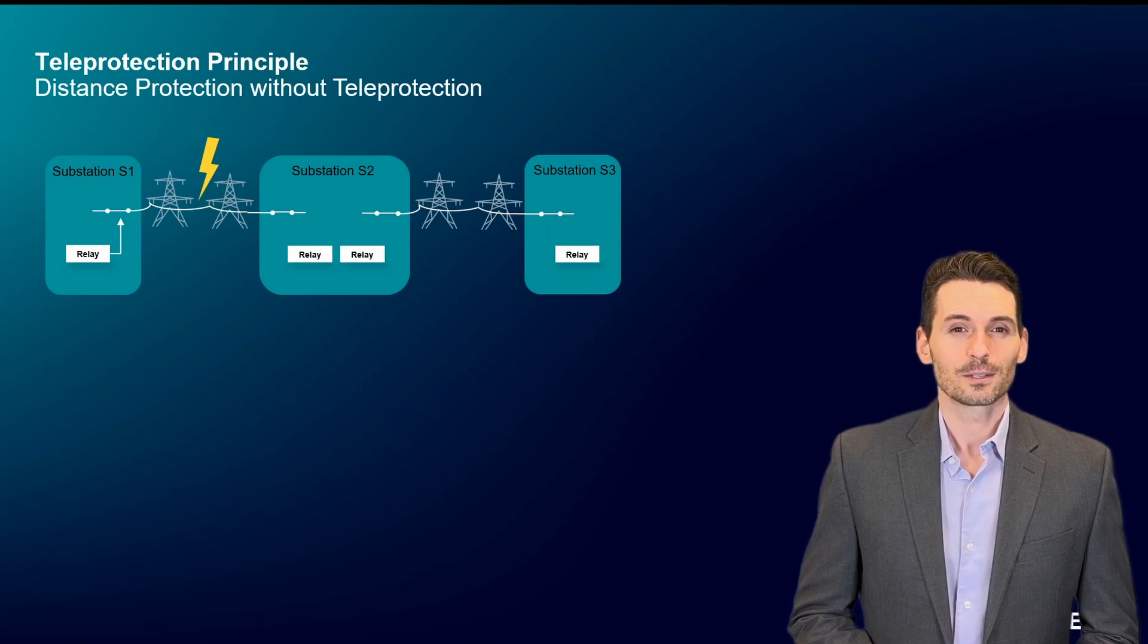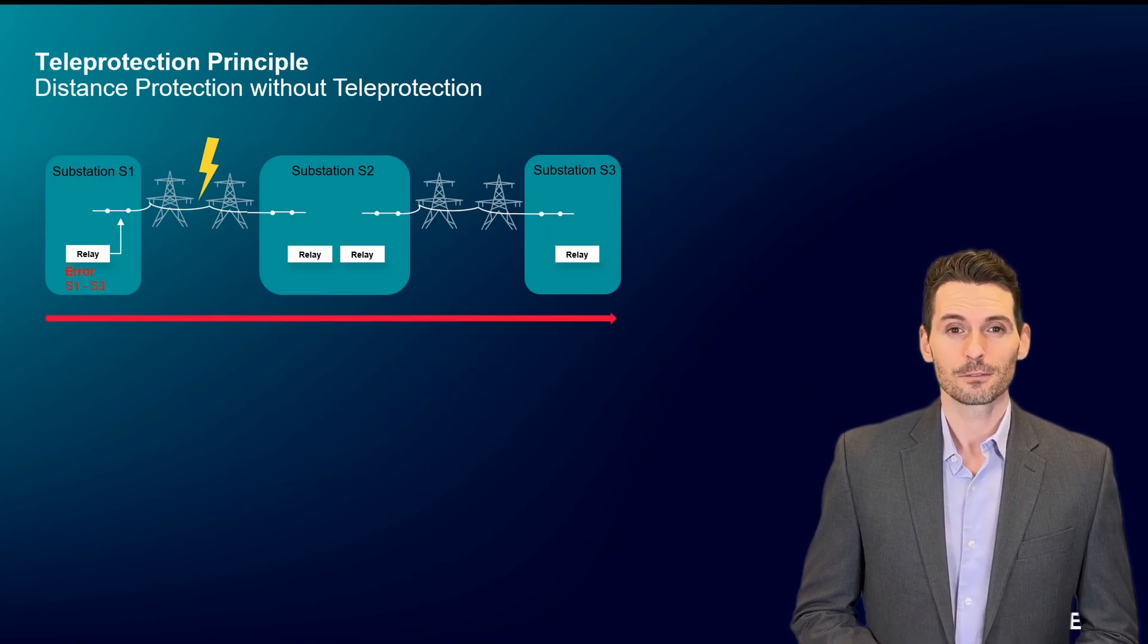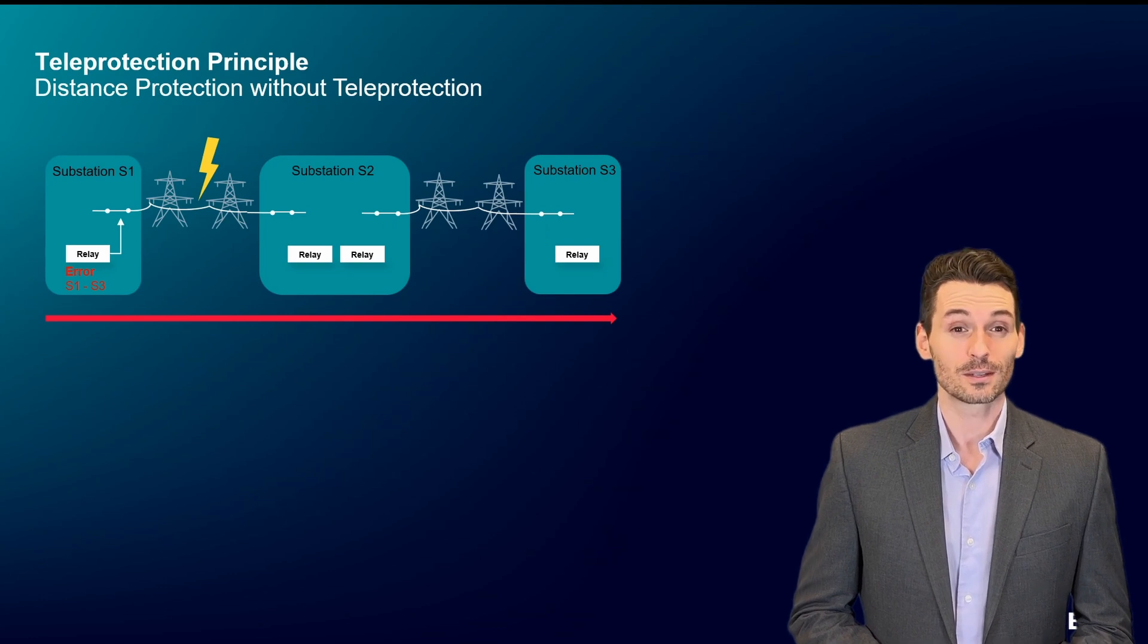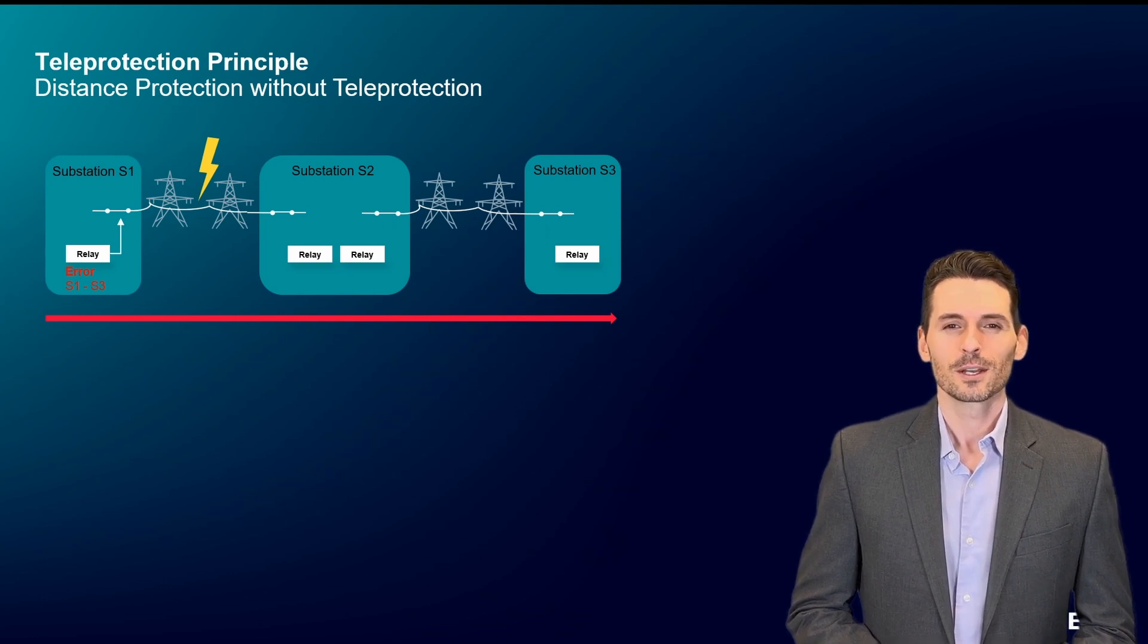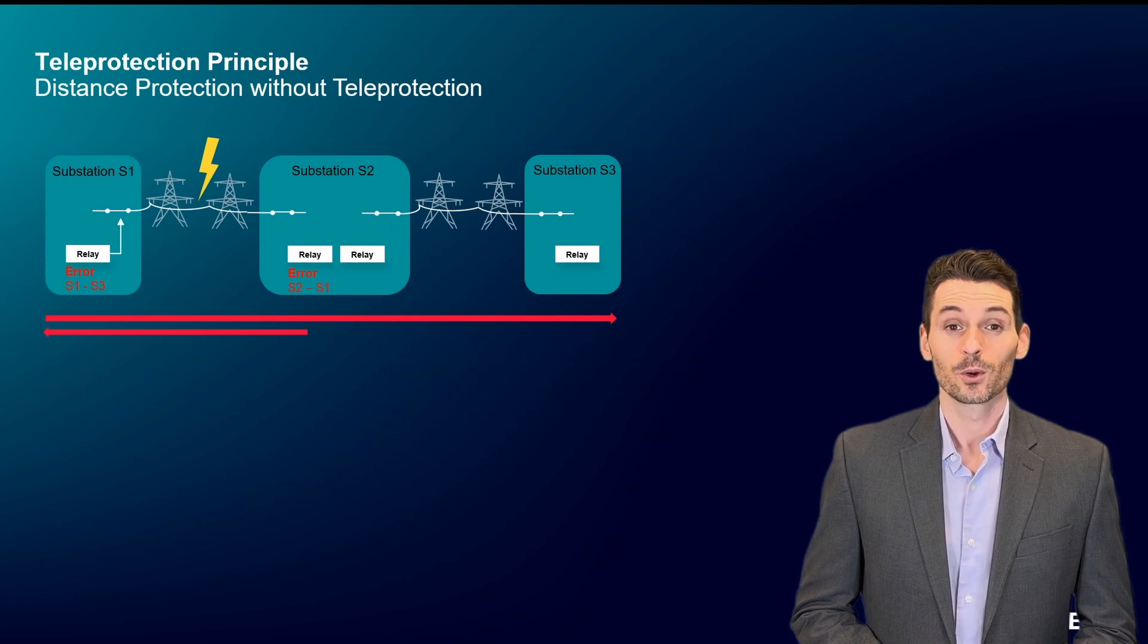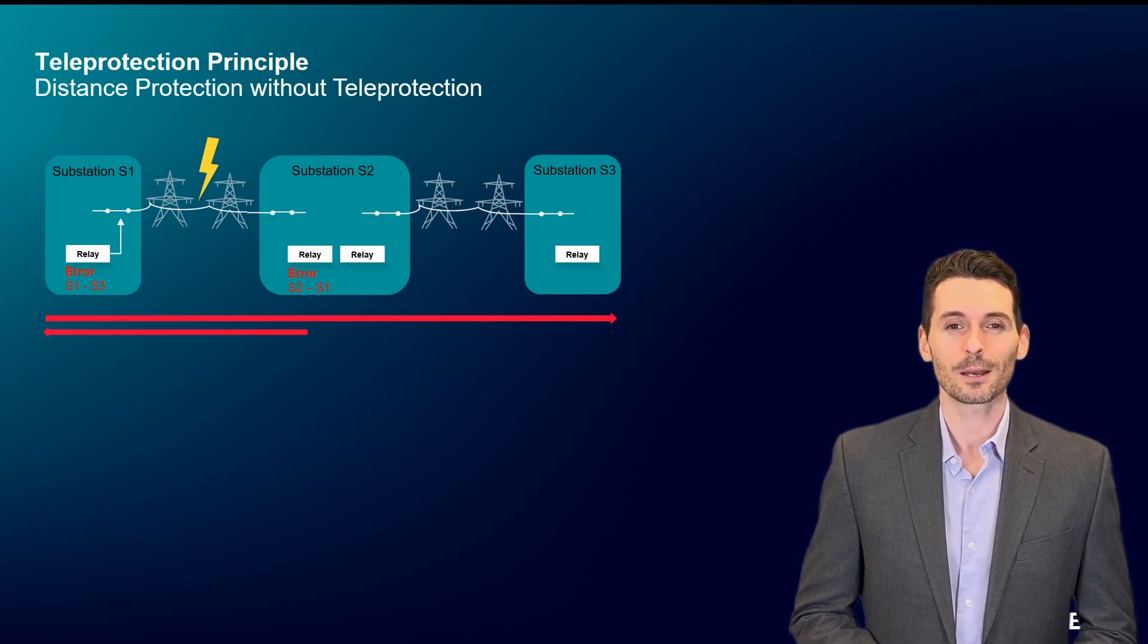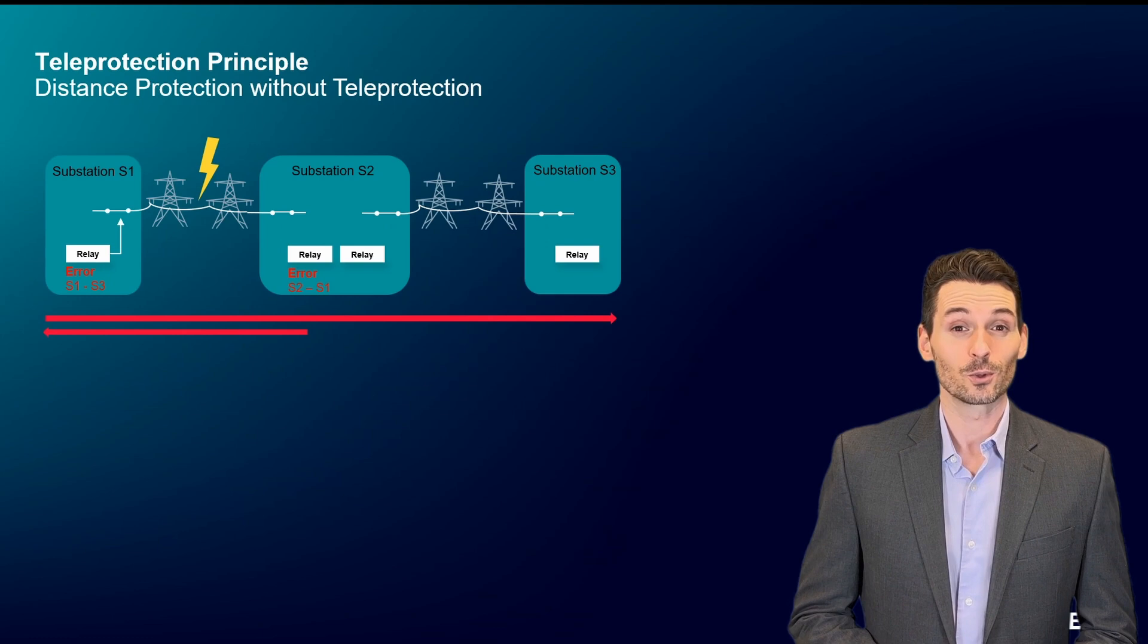Watch what happens to the protection relays. The first relay detects an error. It is only able to locate it between substations 1 and 3. The second relay detects the error as well and locates it between substations 2 and 1.